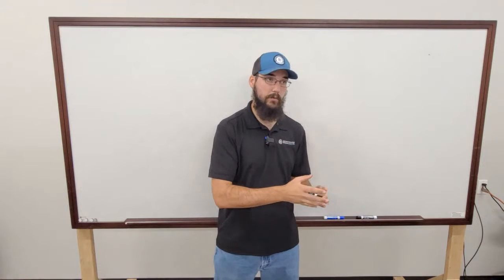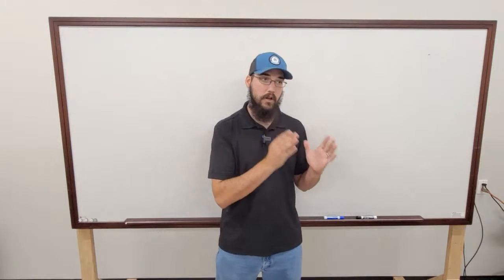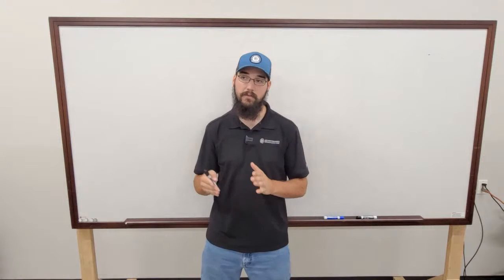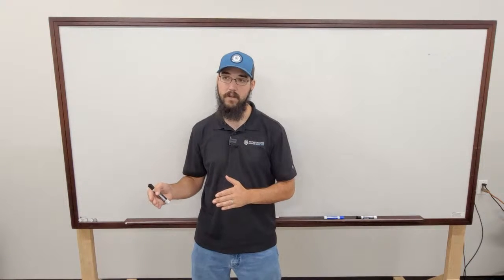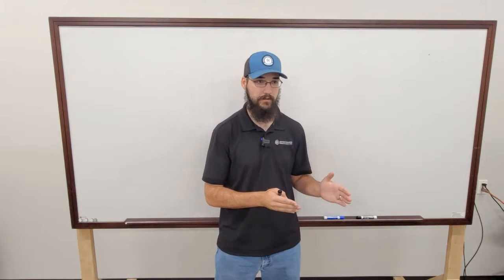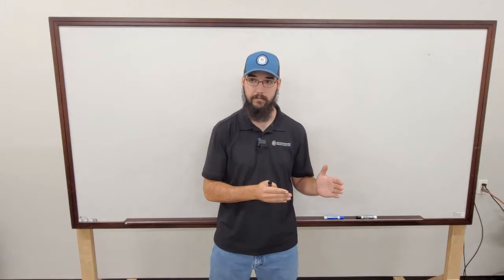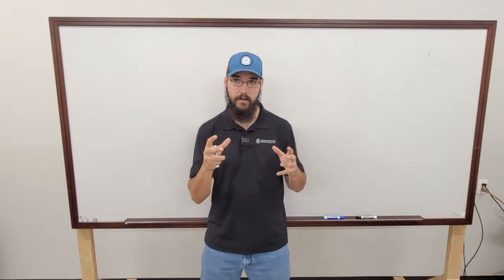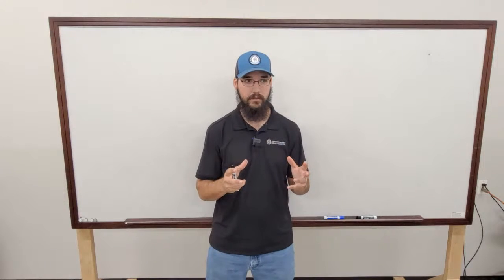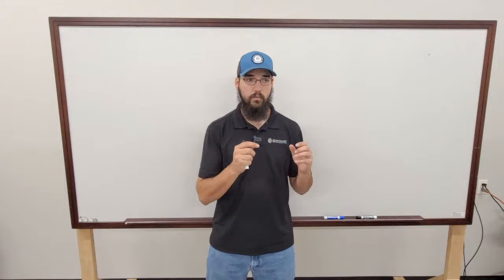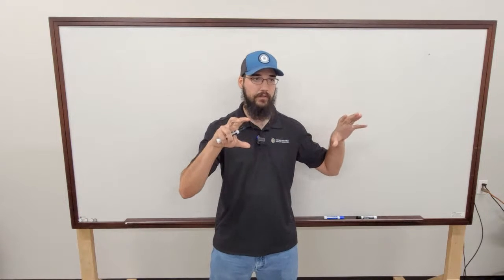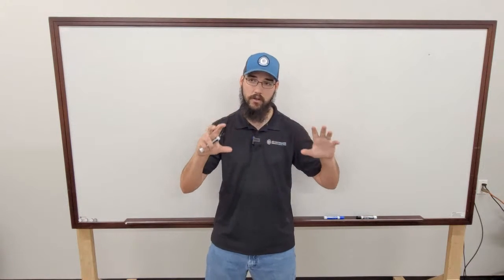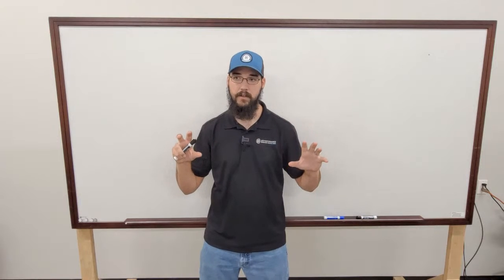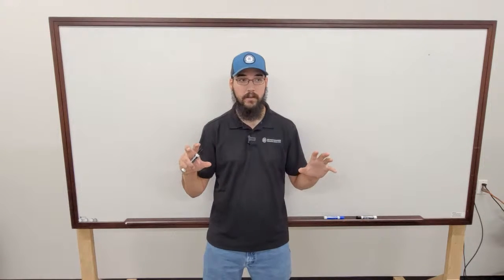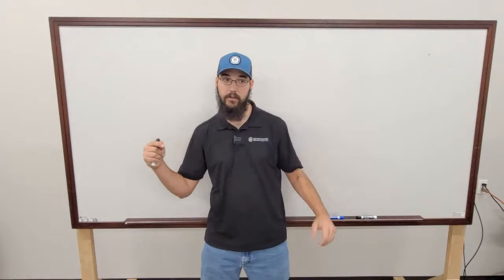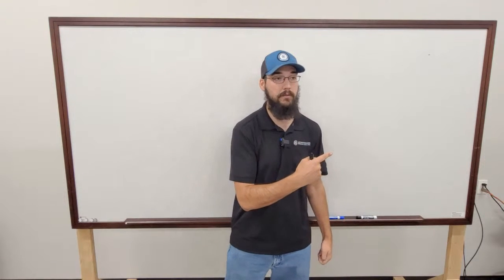With a screw, though, that load percentage is based off of RLA, not valve position. When I say valve, I mean slide valve. And this is a shift in how you think about things.